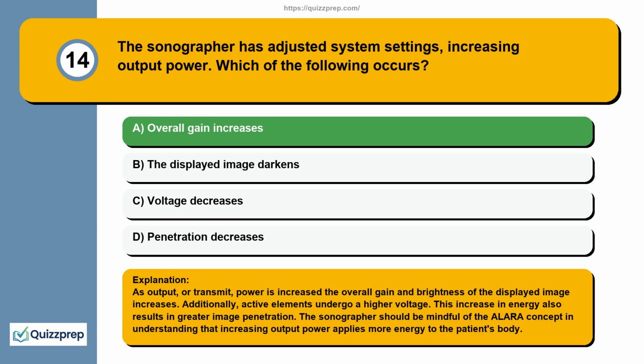As output, or transmit, power is increased, the overall gain and brightness of the displayed image increases. Additionally, active elements undergo a higher voltage. This increase in energy also results in greater image penetration. The sonographer should be mindful of the ALARA concept in understanding that increasing output power applies more energy to the patient's body.